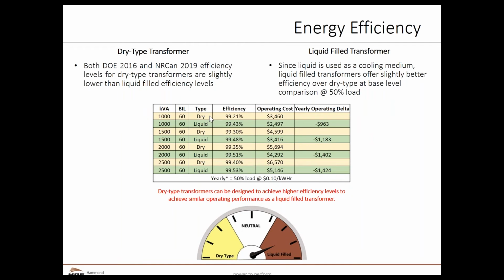Energy efficiency, liquid filled transformers do have an advantage, at least especially for those that are covered by what we call the DOE regulations, or in Canada, NRCan. Generally speaking, liquid filled transformers are going to be slightly more efficient. The requirements by either the US or Canadian Departments of Energy are more stringent for liquid filled transformers, and as a result, they will have slightly better efficiency and a little lower operating cost. Now, we can achieve higher efficiencies with dry type. However, again, that typically involves additional cost. So again, we're talking about just based upon how the transformers are built per the current regulations.